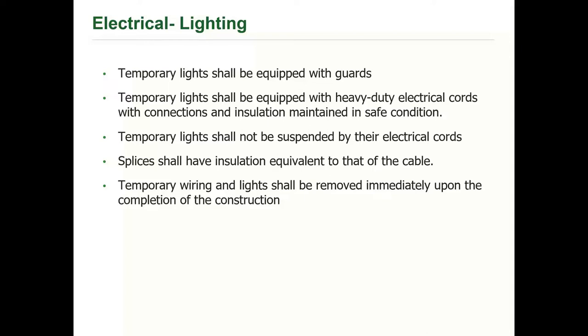Temporary lights should be equipped with guards. You shouldn't be dangling lights by their electrical cords. Any splices should have insulation equivalent to that of the cable. Any open lens lights should have type O bulbs in them, so if they burst, there's an outer bulb to catch any of that hot arcing.